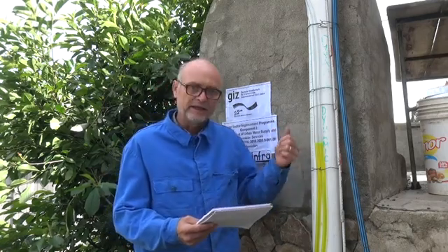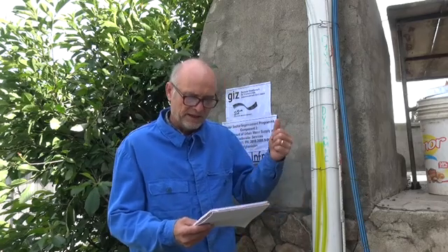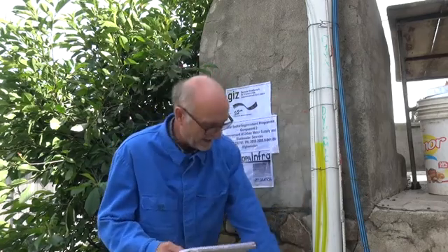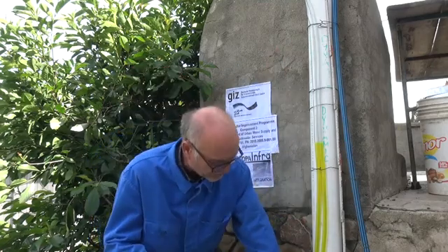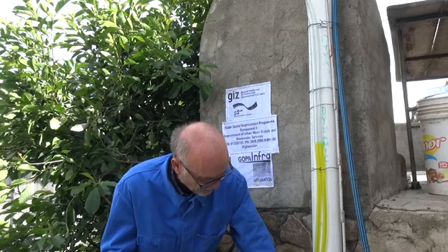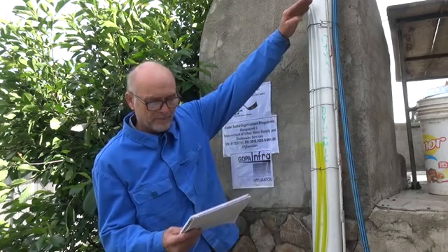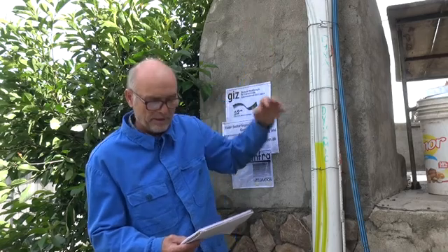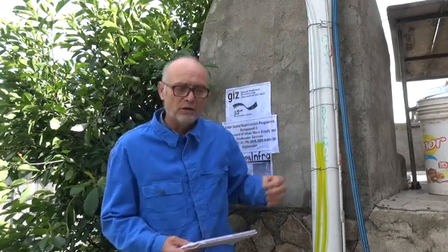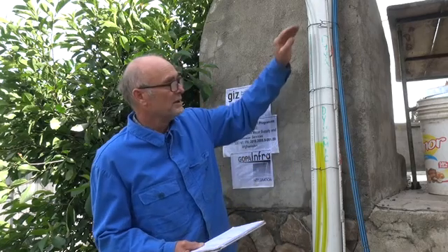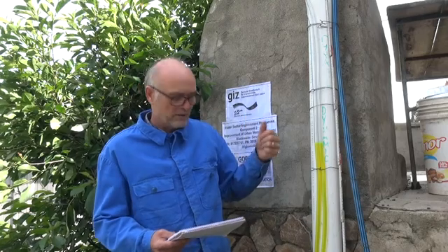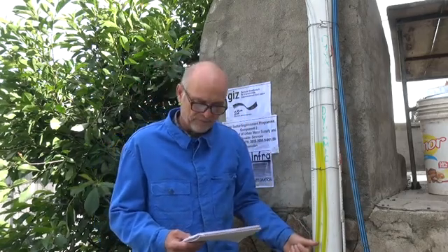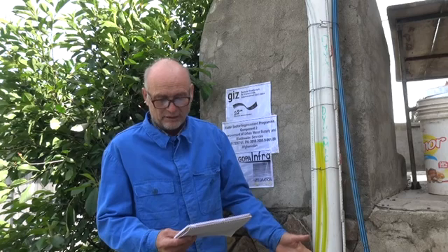That means we can get sand, and we have an extremely high pumping head because the drawdown goes very low. That means that our pump will not be efficient anymore, or it runs out of its optimal operating point. So we have an inefficient pump. We have the risk of sand in the well, and it can also happen that the pump runs dry.